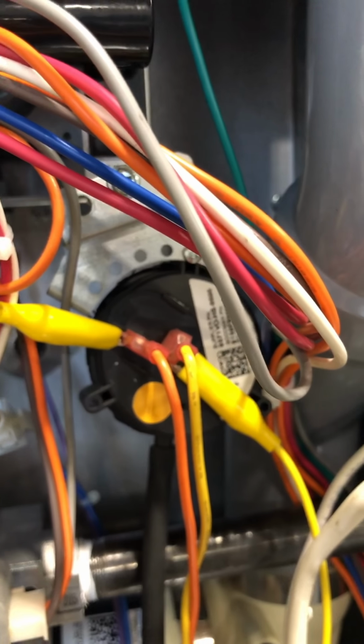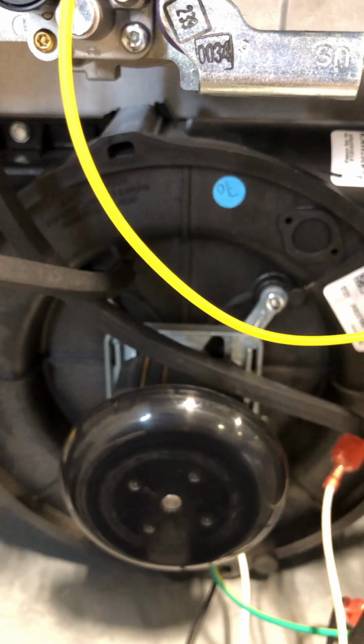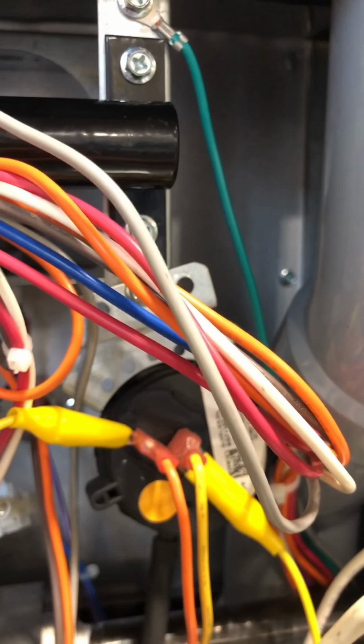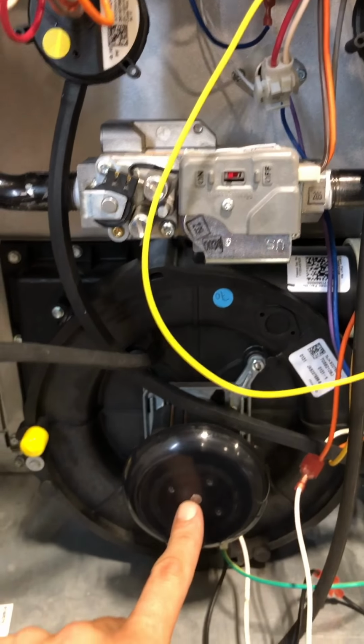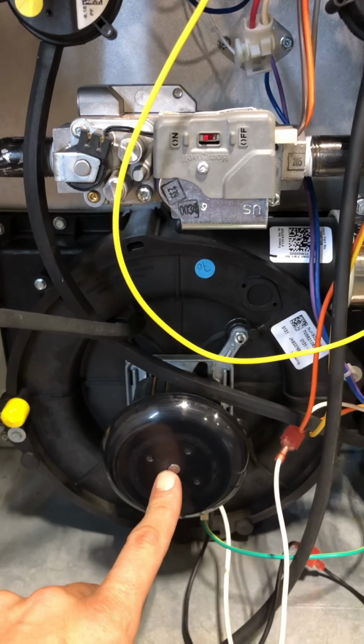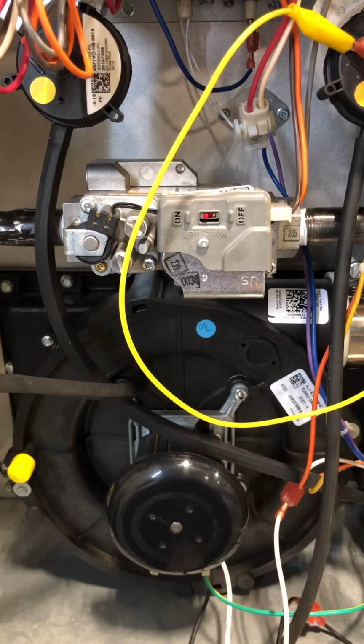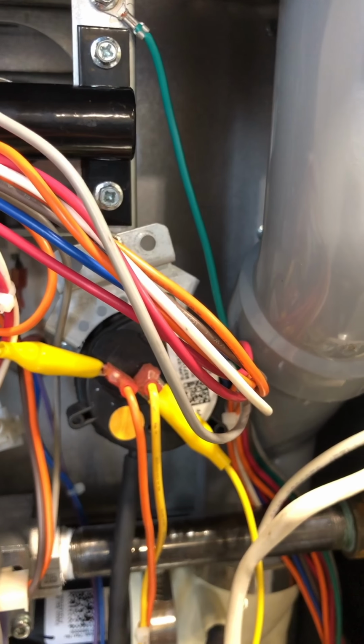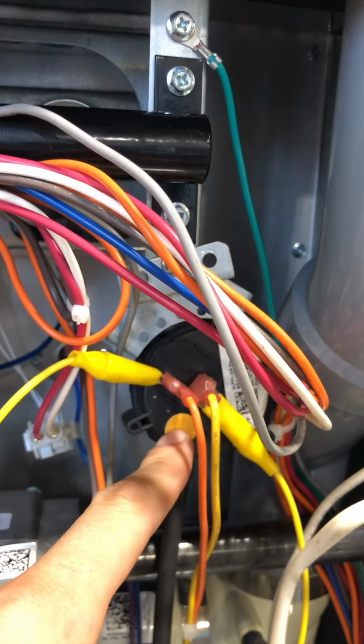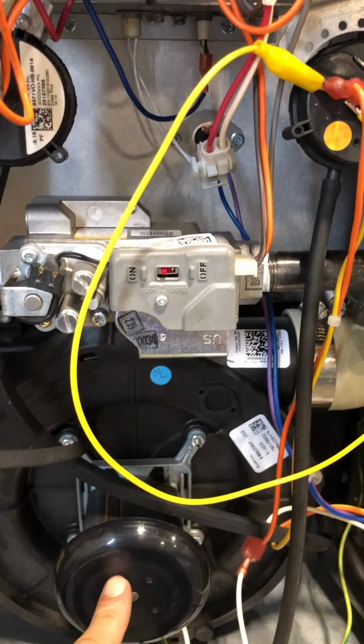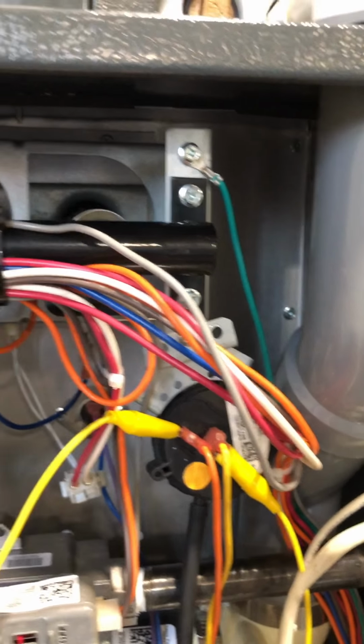So if this stuck closed the last time this furnace shut off, didn't open back up, and then there is a problem with this, and this doesn't start, well, we'll continue through the sequence of operation because this is stuck closed, telling the control board that, yep, the inducer's running, even though it's not. We turn the gas valve on, we ignite the gas, we're burning gas, but we're not getting rid of any of the combustibles that we're creating in that gas chamber, and we create a dangerous situation. This board is going to verify that this switch is open first, to verify that that switch is actually operating correctly, and then it will start the inducer. And then if everything is running correctly, this inducer will pull enough of a vacuum on this switch, then that switch will close and will continue the process.